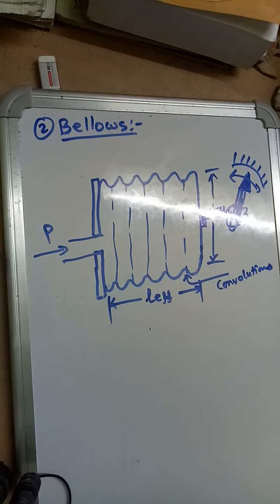The generally accepted methods of manufacturing bellows elements are by turning from a solid stock of metal, by soldering or welding stamped annular rings, rolling a tubing, and by hydraulically forming a drawn tubing.